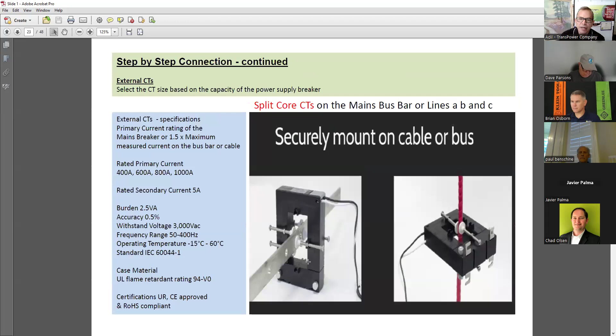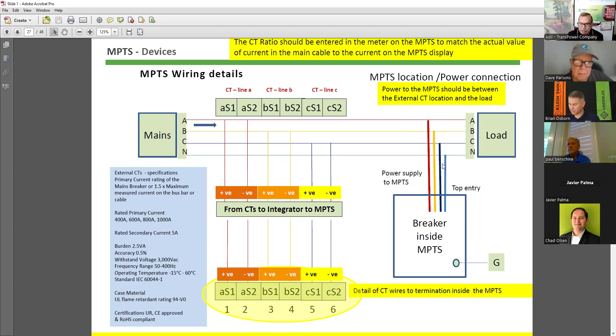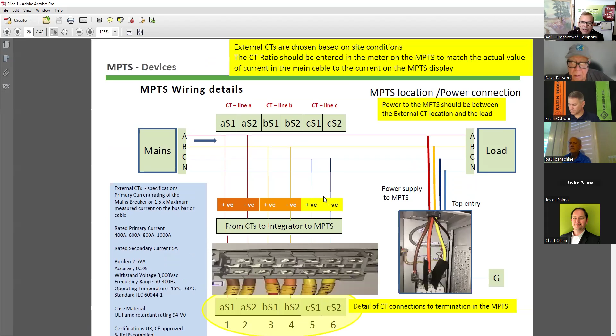Yeah, of course. You see this one-line diagram? The main power comes in here, which could be from your main disconnect or from a transformer, and it connects to the bus bars. On this bus bar, you're tapping the CTs. Then the point of coupling to take power out is downstream of the CTs, and all the load MCCBs on your switchgear are downstream of this point of common coupling. You've heard the term POCC, point of common coupling?